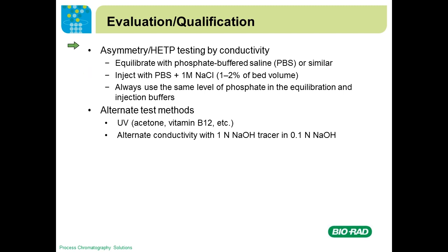Now you're ready to do asymmetry and HETP testing. You can do it two ways. Many people use conductivity: equilibrate the column with phosphate buffered saline, then inject PBS plus up to 1 molar sodium chloride, typically 1 to 2% of the bed volume. Always use the same level of phosphate in both equilibration and injection buffers — mismatching can produce odd-looking peaks. If you don't want to use conductivity, people have also used UV tracers such as acetone, vitamin B12, or caffeine.